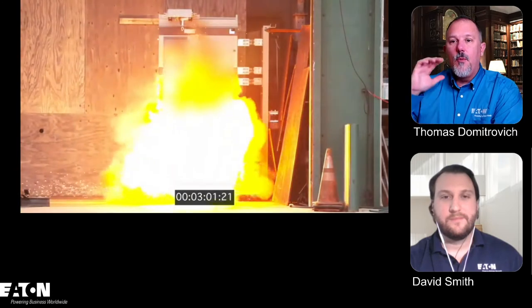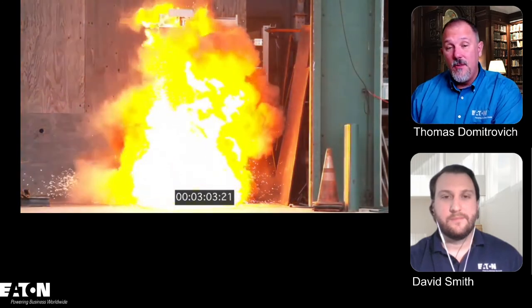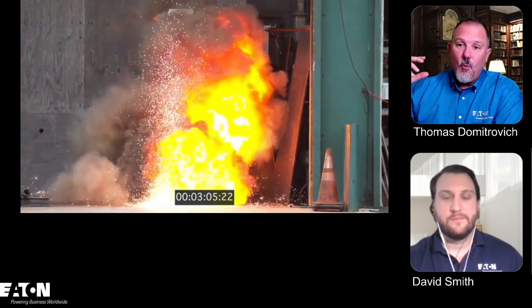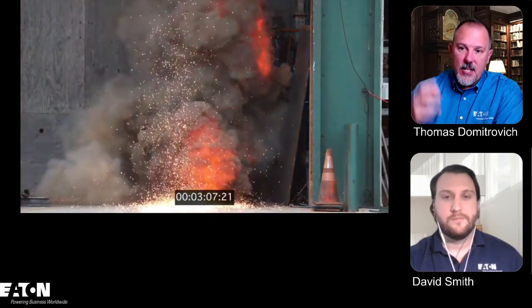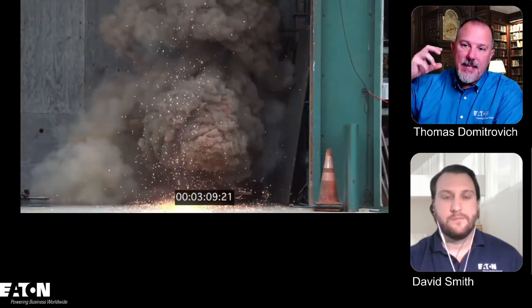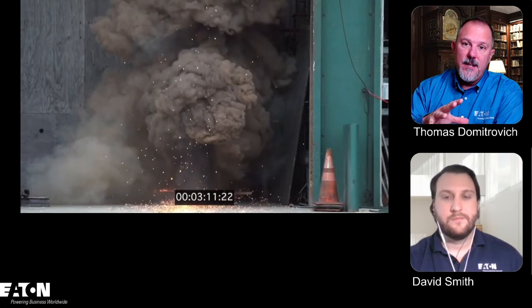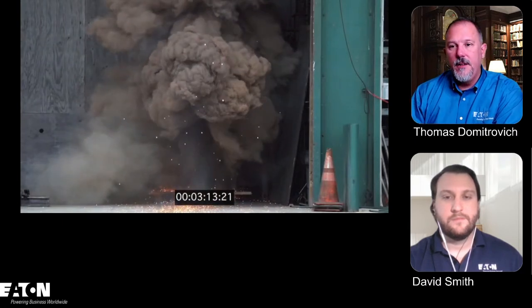There's the arc quencher. Let's watch this one. Ooh. 85,000 amps, a low voltage assembly. This is the amount of energy that you'll have. Now, what we're going to show you in the next video is the arc quenching technology taking this exact same event and reducing the clearing time.